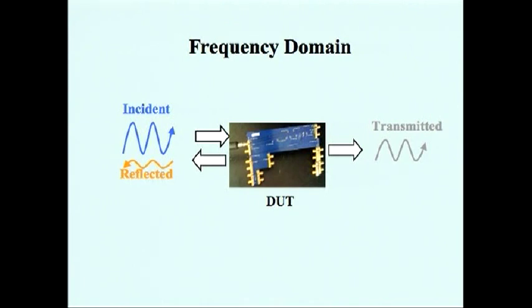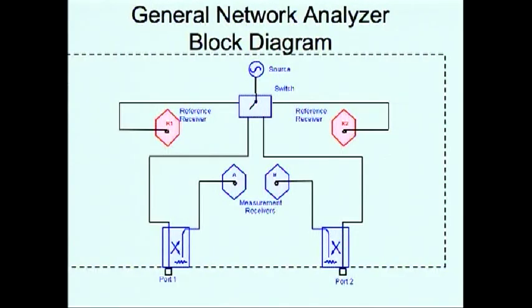A network analyzer analyzes a circuit or device under test by comparing the signal that is applied to the circuit, the incident signal also called the reference signal, with a signal that goes through or is reflected from the circuit. The network analyzer needs to control the reference signal to provide an accurate comparison.